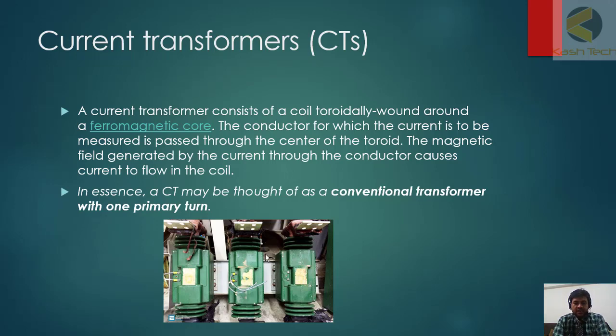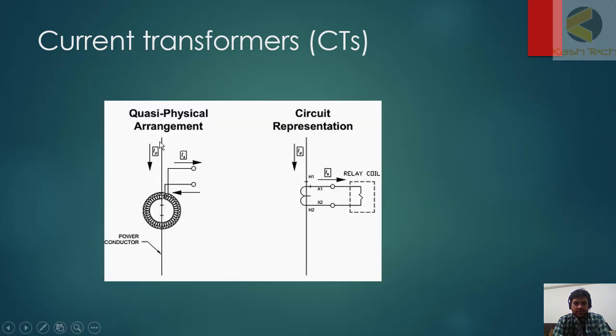I will explain in the next slide the details of this definition. Here you can see this picture of CT, how CT looks like in MV switchgear. As we have already read the explanation of CT, you can see this is the primary side of CT, which is basically a conductor. It will be treated as a single turn.